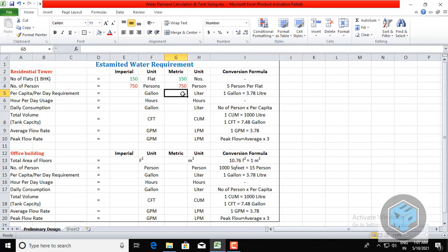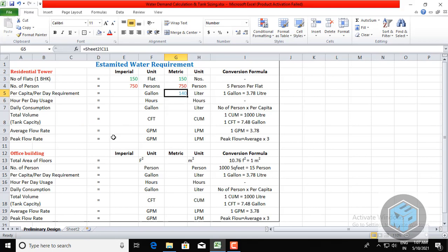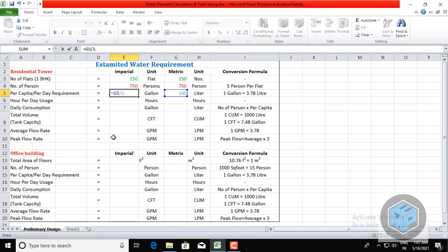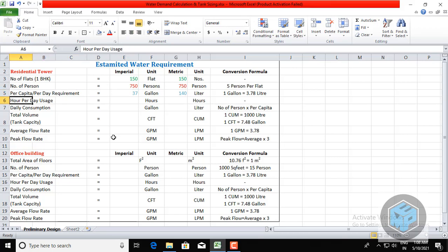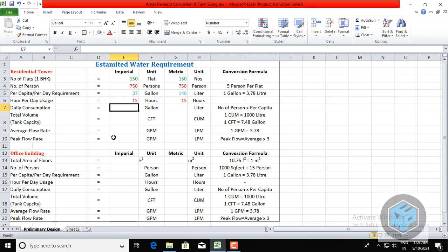So in the metric section, the per capita per day requirement is 140 liters. Converting to gallons: 140 divided by 3.78 (since 1 gallon = 3.78 liters) gives approximately 37 gallons. Hours per day usage is taken as 15 hours — the total consumption hours considered is 15.